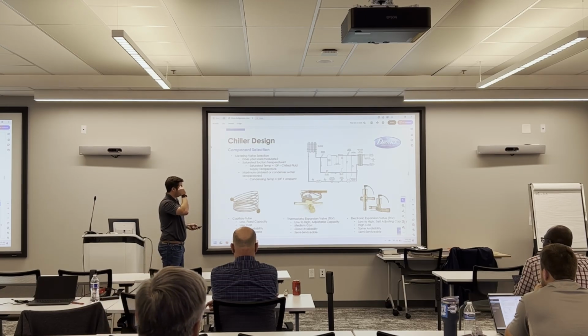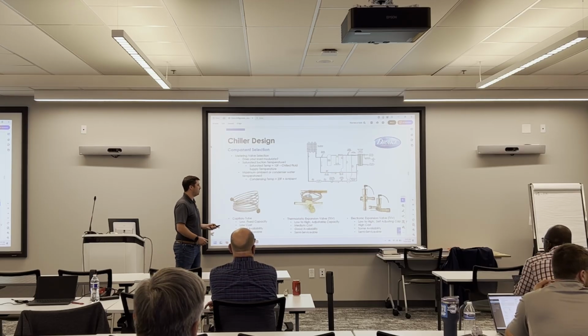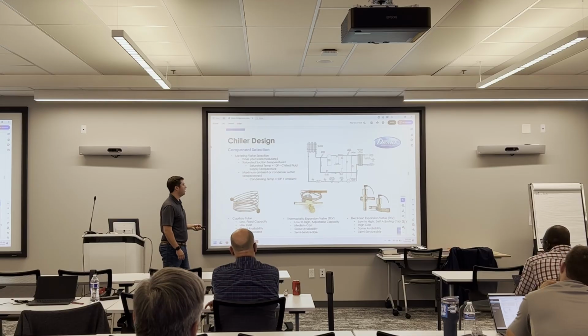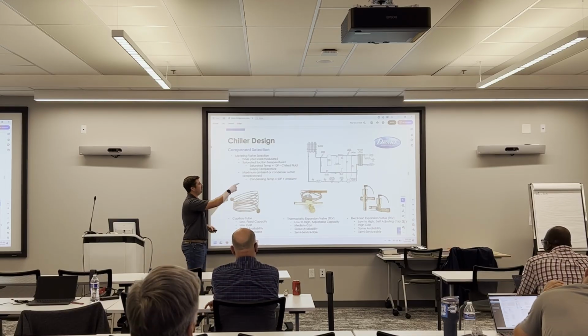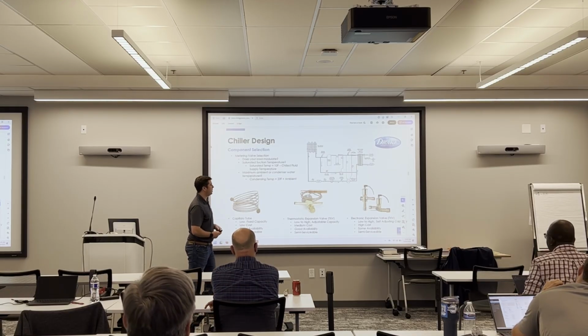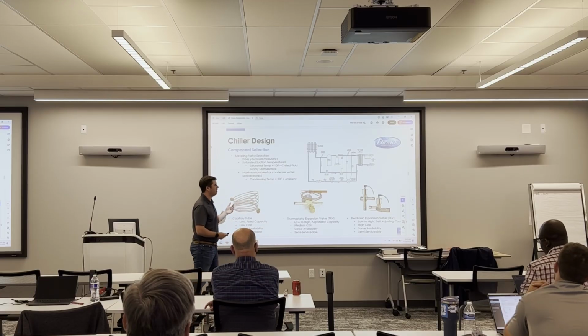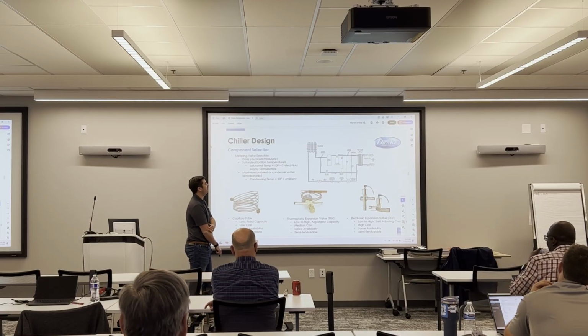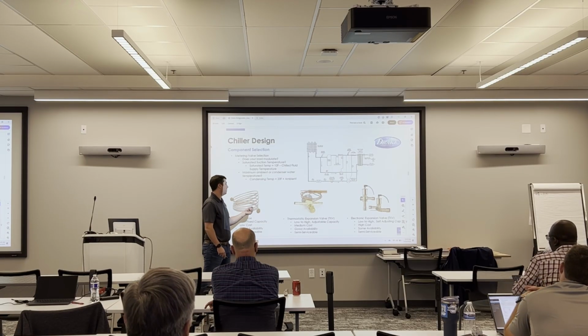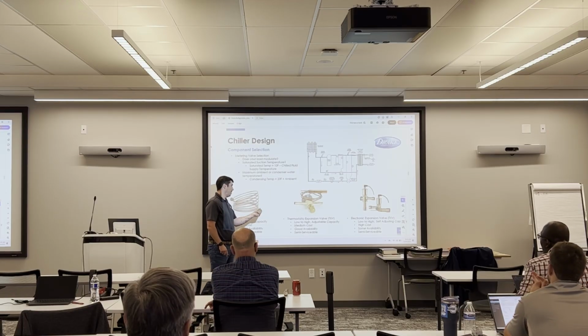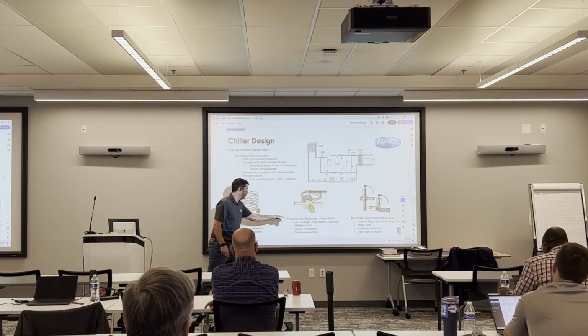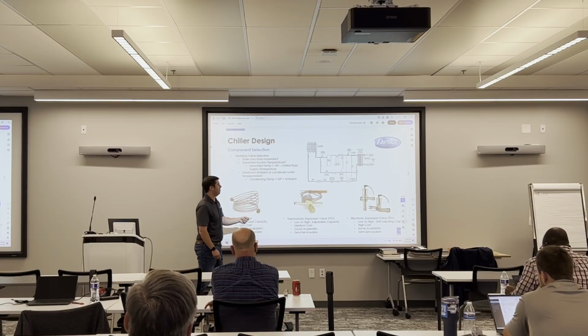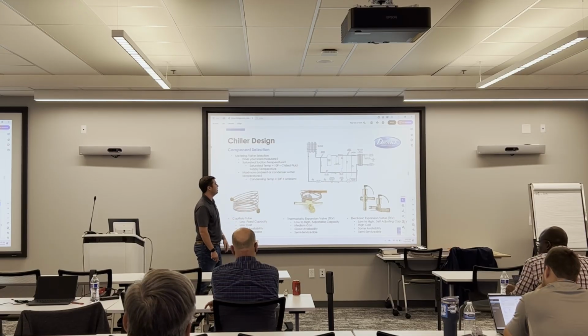Our bread and butter is our thermostatic expansion valve. We call them TXVs. Low to high cost, and you can actually adjust the capacity. There's a spring you can set in here to get a desired superheat out of the evaporator. So if my refrigerant going through my evaporator is moving too quickly, it might not be boiling off all the liquid refrigerant. And what we'll do is we'll have the contractor, the tech, go in there and make an adjustment to the spring on the TXV, essentially increase the pressure of the spring, which allows less refrigerant to flow through, which gets you more superheat ultimately.